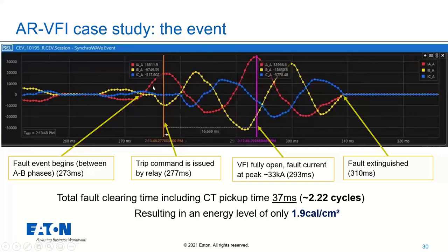So this is the sensing, the pickup by the CTs, the communication of that fault to the relay, and the sending of the trip signal. And when you see that orange line, that's the issuance of the trip signal to the internal vacuum interrupter, and then the interrupters open and clear. And in this case, extremely fast overall clearing time.